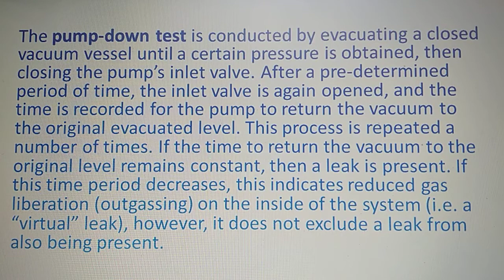Next is the pump down test. This pump down test is conducted by evacuating a closed vacuum vessel until a certain pressure is obtained, and then closing the pump's inlet valve. After a predetermined period of time, the inlet valve is again opened and the time is recorded for the pump to return the vacuum to the original evacuated level. This process is repeated a number of times. If the time to return the vacuum to the original level remains constant, then a leak is present. If this time decreases, then this indicates reduced gas liberation or outgassing on the inside of the system, that is a virtual leak. However, it does not exclude a leak from also being present. So this is about the pump down test.